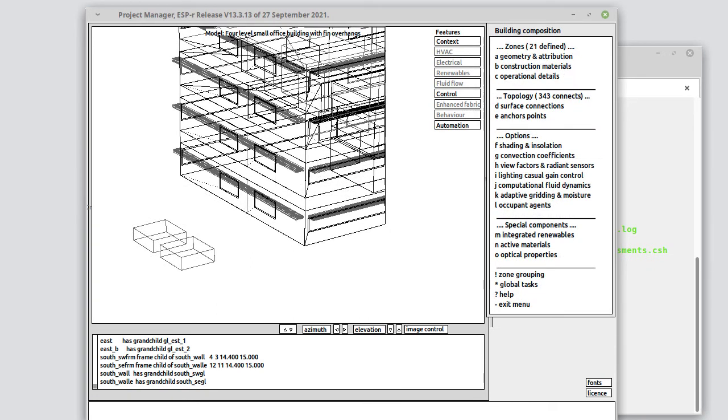The model includes two zones representing mixing boxes for supply and return to temper fresh air into the building. However, this is represented by attributes within the zone operations files and fixed rates of ventilation between these mixing boxes and the occupied spaces. This is a relatively old representation of mechanical ventilation systems. We could potentially do quite a bit better than that.